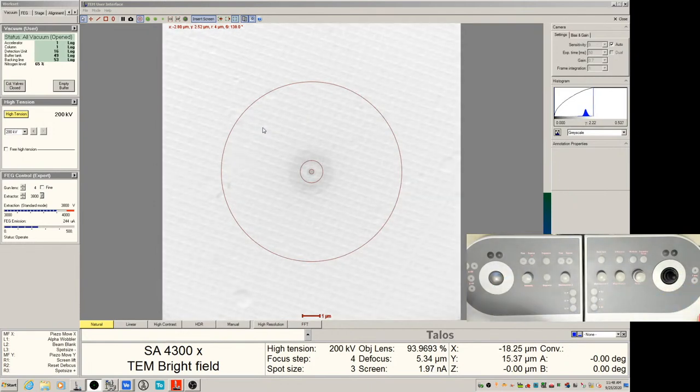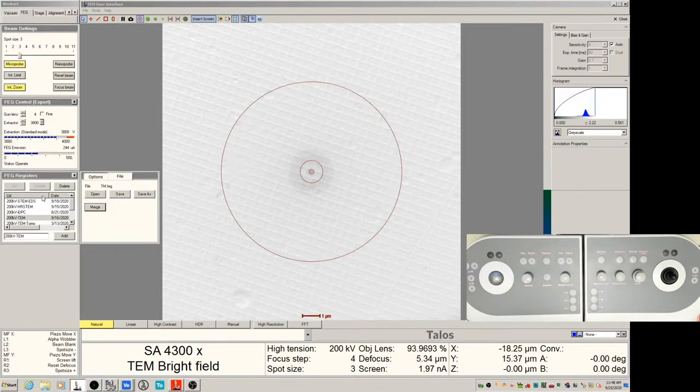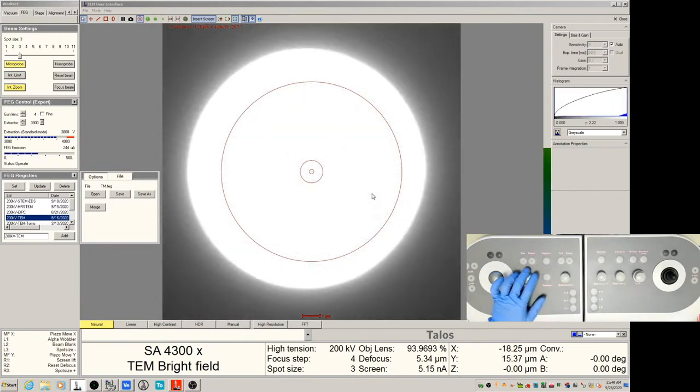Now, if you go to the SOP, we are now at 3.2 TEM alignment. So it says load 200 kV TEM alignment. That's what we just did. We click this and set. Now we're in TEM mode, and then we will need to find the eucentric height. So from here, we are really going into the alignment procedures.